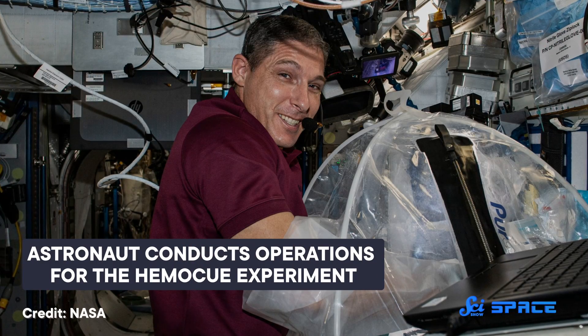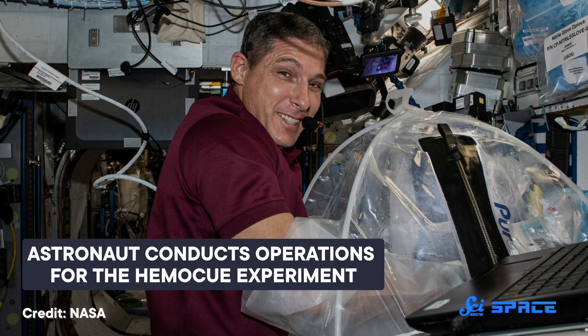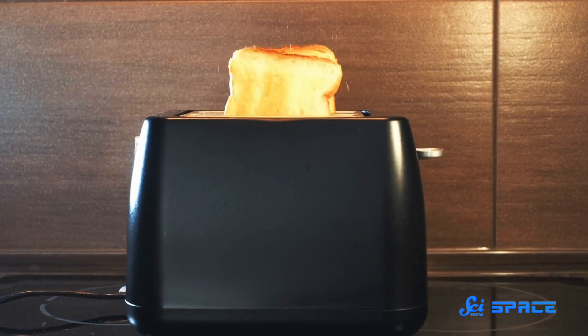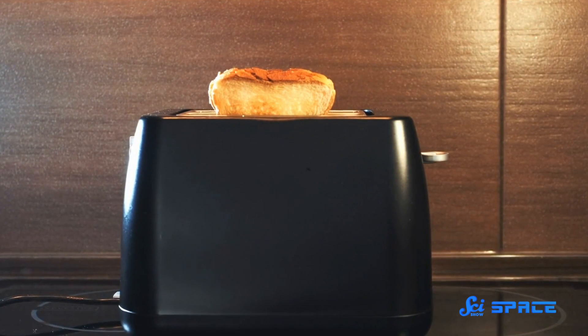But all that may be about to change thanks to an innovative blood analysis technology called HemoCue. HemoCue is the first machine to successfully analyze white blood cells in space, using only the tiny prick of a finger. It requires less than a milliliter of blood for the test, which saves a lot of time and effort compared to dealing with tubes full of blood. Better still, the approach doesn't require any added liquid substances, like those typically used for terrestrial blood analysis. Plus, the device is small — about the size of a toaster — and the small sample size gets around a lot of the hassles that microgravity creates for traditional techniques.